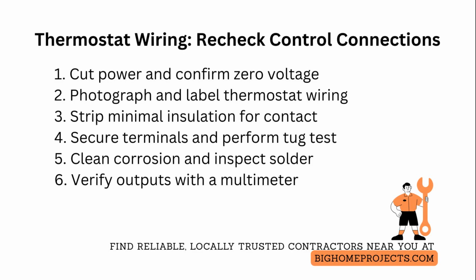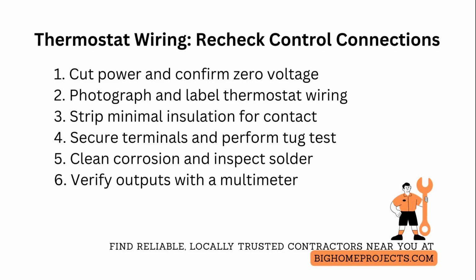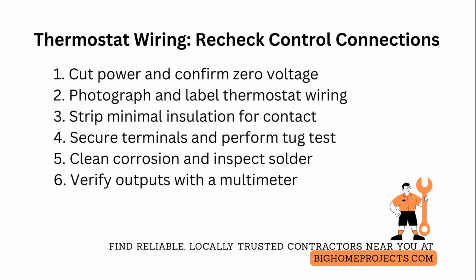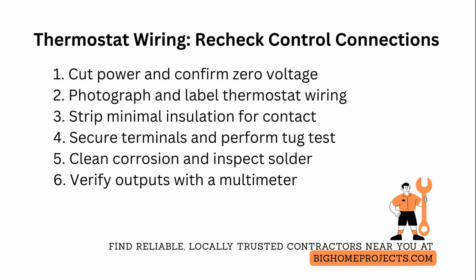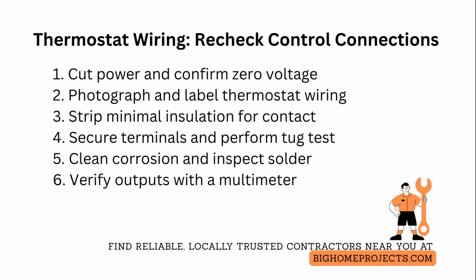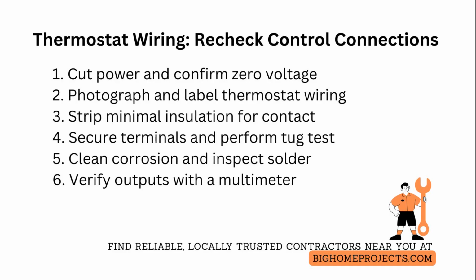Match common wire functions to the new thermostat's requirements. Heat call, cool call, common, fan, and 2-stage or variable control leads. And map any manufacturer-specific control pins against the board diagram. If the control board has removable terminal blocks, seat them fully and secure the mating connector clips. Loose block seating is a frequent intermittent fault.